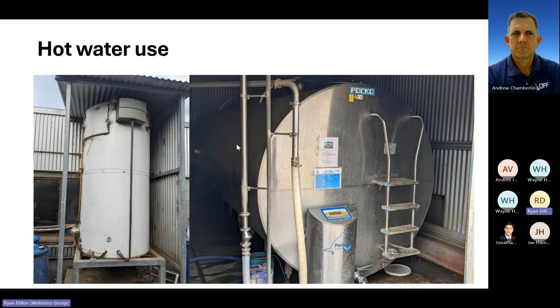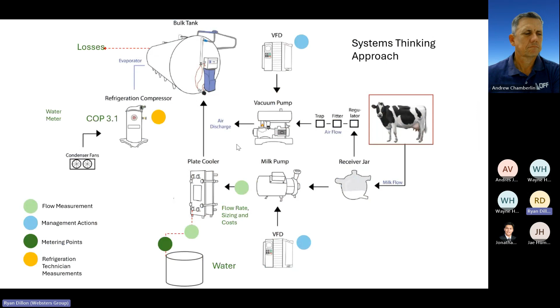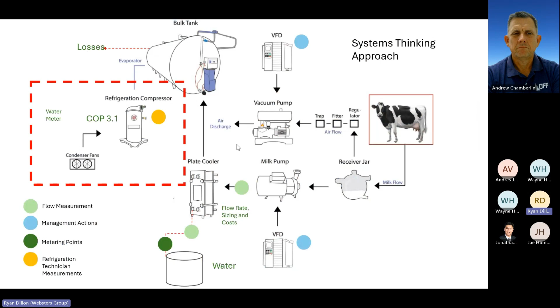It's either an element heating up. How do we capture heat? How do we reuse heat? How do we think from a systems perspective? Where am I wasting heat? Where can I reuse it to fill this larger electrical energy use in dairies? So when you actually take a systems thinking approach, think of what's used what and where and when. Through this, we identified refrigeration compressors rejecting a significant amount of heat. And in this case, you're actually able to install an inline hot water system that recovers heat from the condenser.